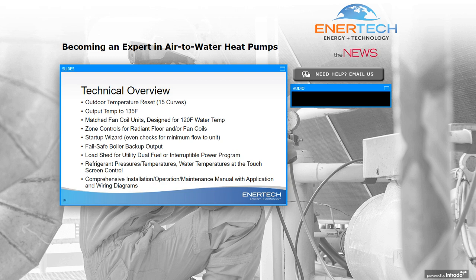With an outdoor temperature reset curve, we can choose what our maximum water temperature should be at design temperature and what our other temperatures are when it's milder. That's really where we're going to maximize the efficiency, and that's built into the control, another advantage of having the two pieces packaged together. The output temperature up to 135 degrees Fahrenheit is a big benefit for domestic hot water. We may not need 135 degrees, but it's available if we need it, and that will be used primarily for domestic hot water. It certainly could be used for other applications.